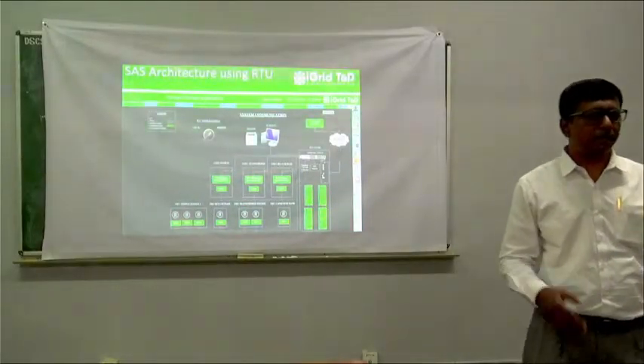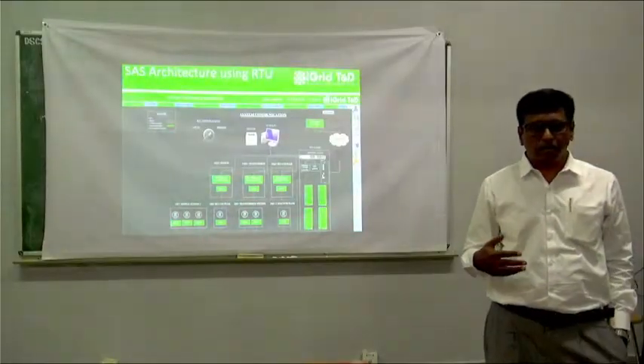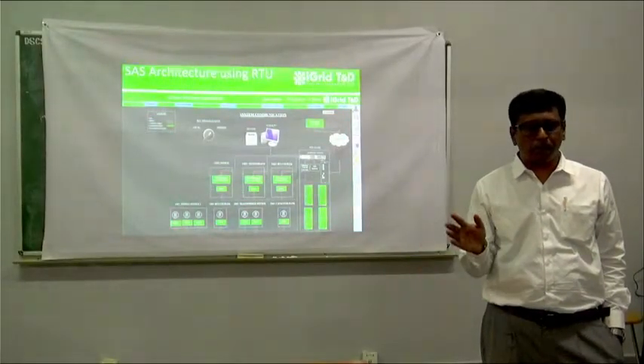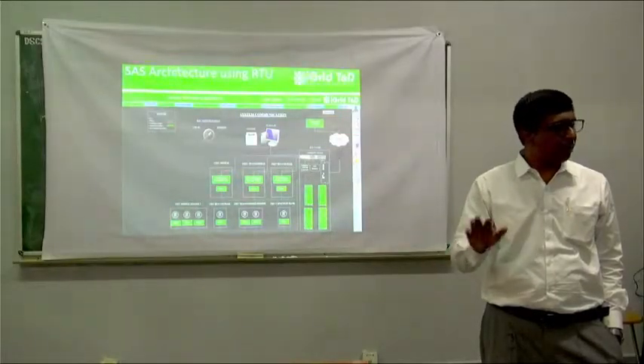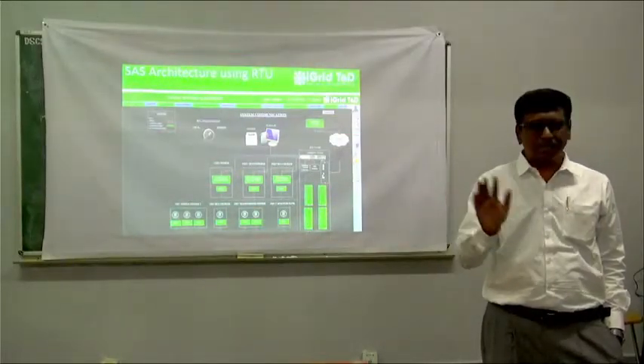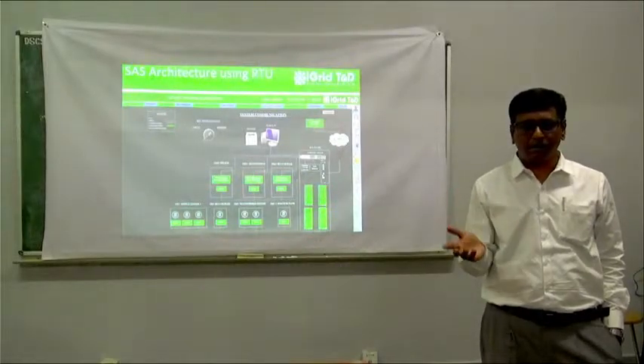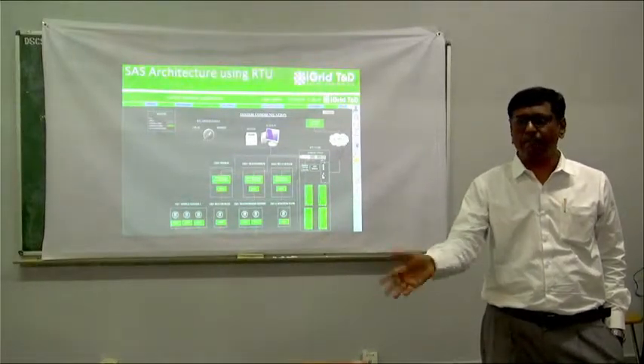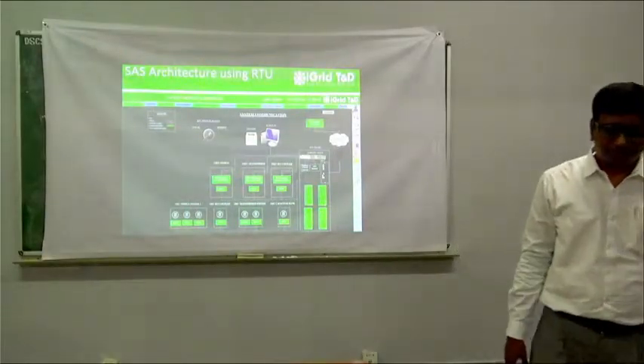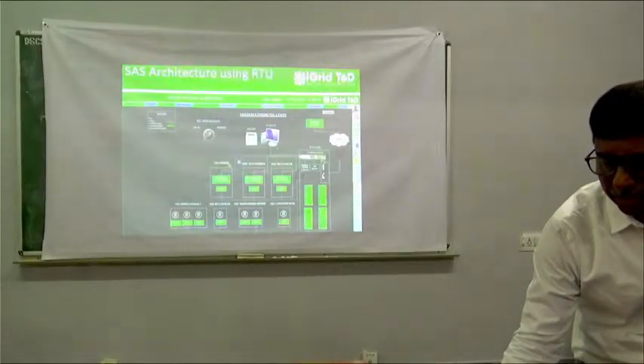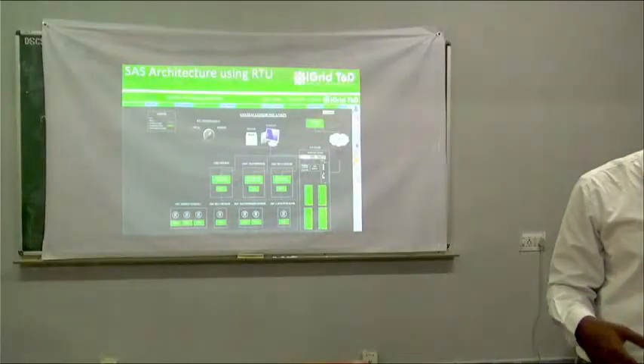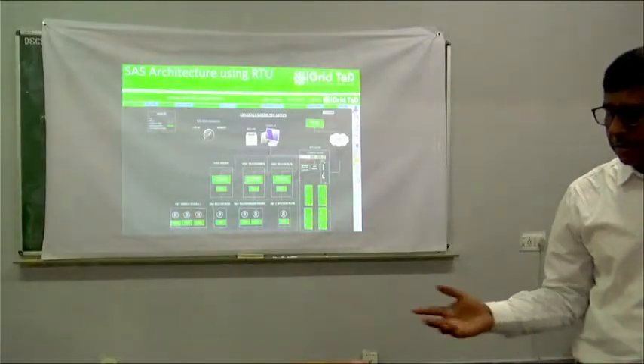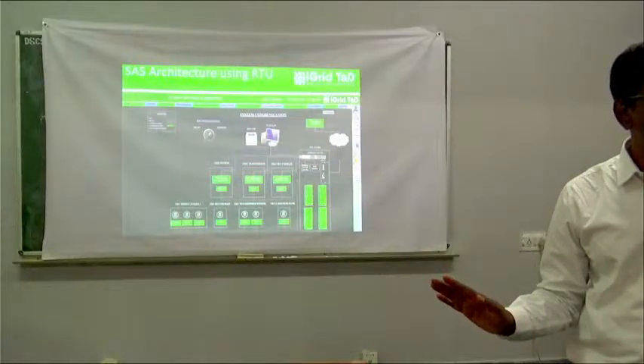Yes. So that is why, again I come back to what we have done in Karnataka. We have been approved for both. We call this an RTU panel, and the other one we call a SAS panel. What is the difference between a SAS panel and an RTU panel? The SAS panel will have a BCU, whereas an RTU panel will have my RTU units. Okay. So here, if you observe, it's a combination. It depends. For example, in Madhya Pradesh and Karnataka, they don't use a SAS panel. They use an RTU panel. The only difference is I am using an RTU instead of a BCU for control operation.